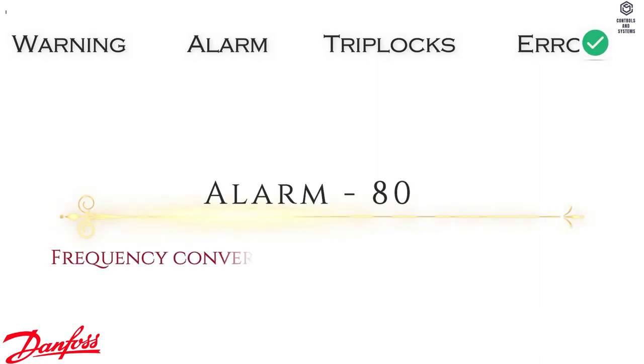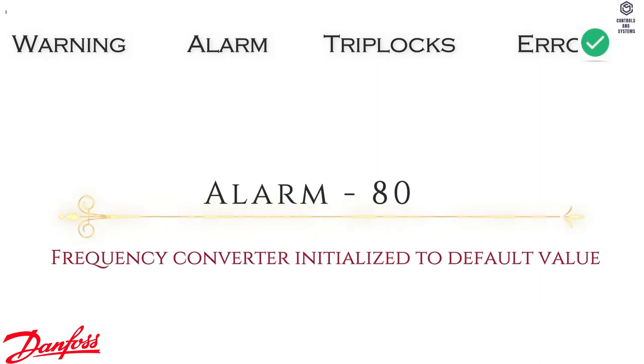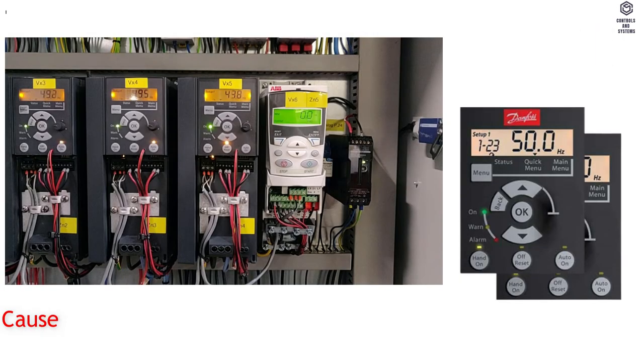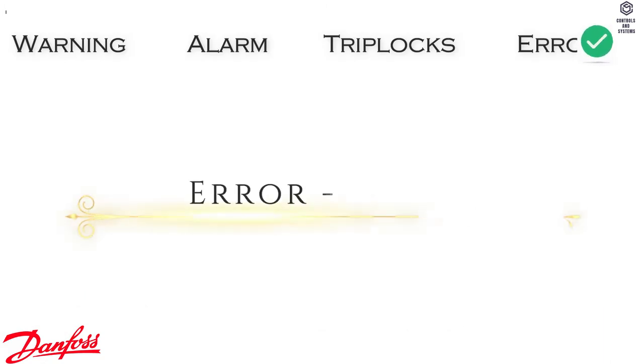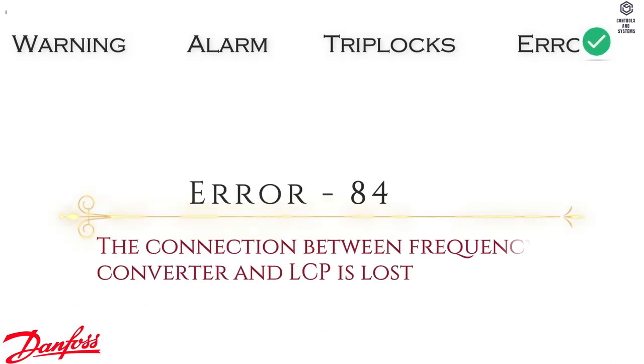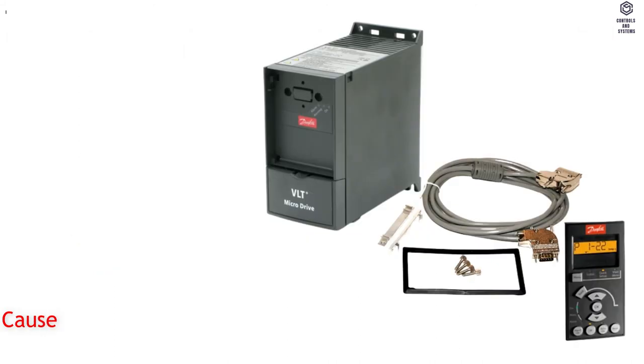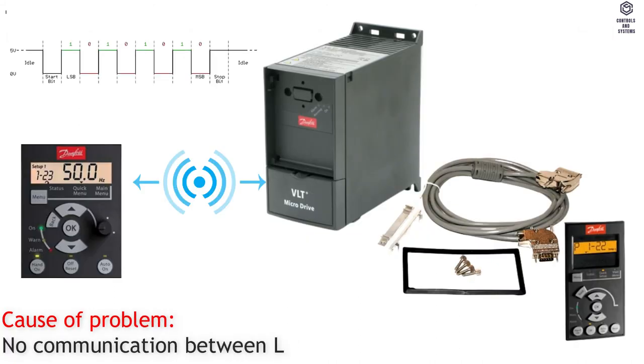Alarm 80: Frequency Converter Initialized to Default Value. Cause of Problem — all parameter settings are initialized to default settings. Error 84: The connection between frequency converter and LCP is lost. Cause of Problem — no communication between LCP and frequency converter.